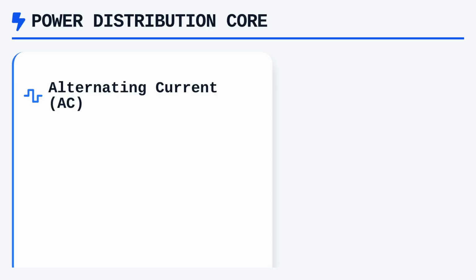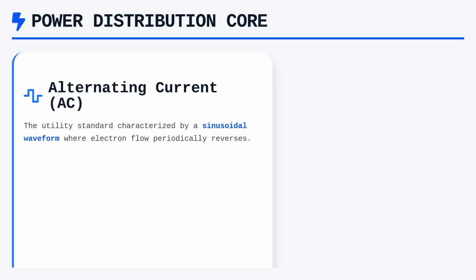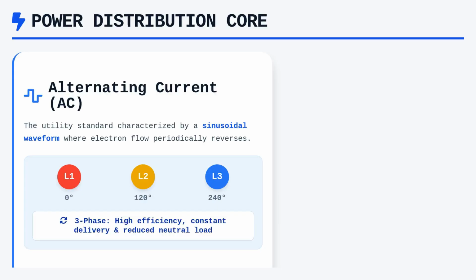Alternating current is the standard for utility power, characterized by its sinusoidal waveform where the direction of electron flow periodically reverses. Within the context of a telecommunications facility, we typically deal with three-phase power, which is chosen for its efficiency in delivering high loads to large-scale equipment environments. In a three-phase system, power is transmitted via three conductors carrying currents that are offset by 120 degrees, allowing for a constant power delivery that reduces the need for heavy neutral wire return paths in balanced scenarios.